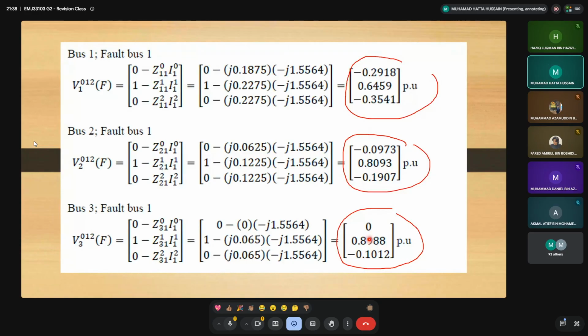So when I compare the voltage at bus 1, the voltage at bus 2, and the voltage at bus 3 for zero sequence, positive sequence, and negative sequence, we can have different values. We know that when the fault occurs at bus 1, the voltage at bus 1 is smaller than the voltage at bus 2 and also the voltage at bus 3, which means that when the fault occurs at bus 1, the current will become high and the voltage will reduce until it is approximately equal to 0.